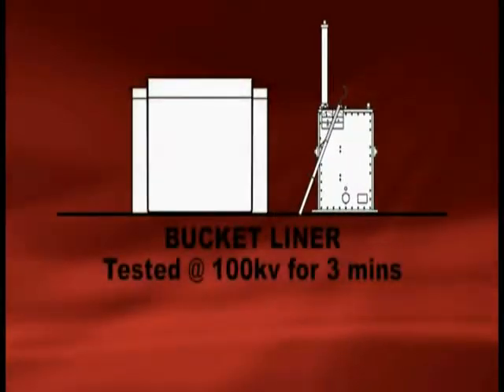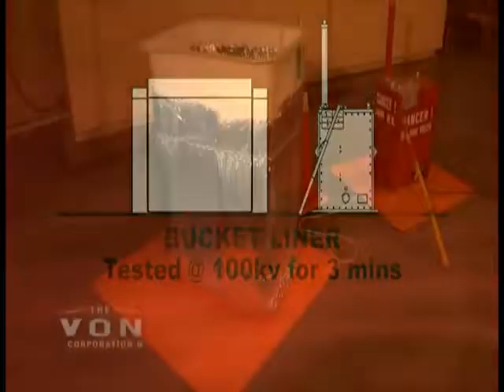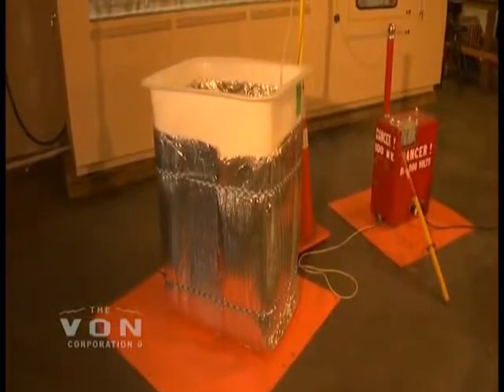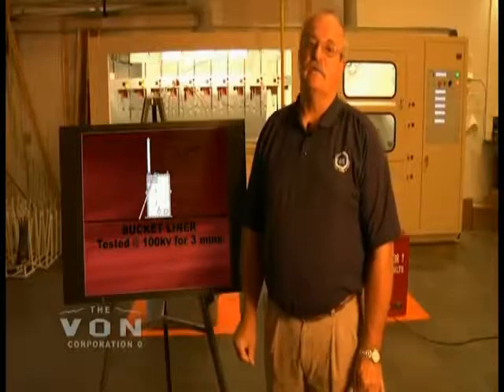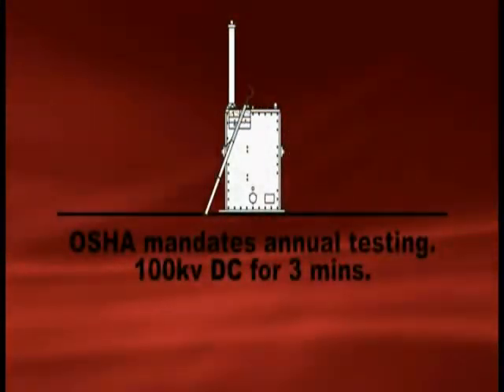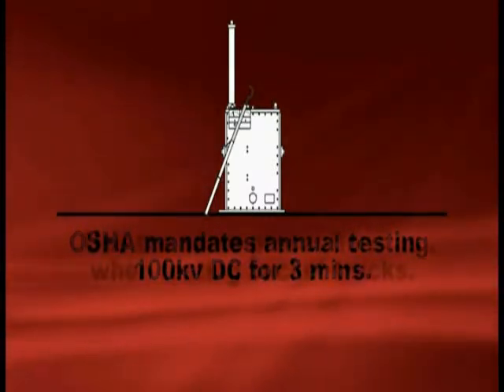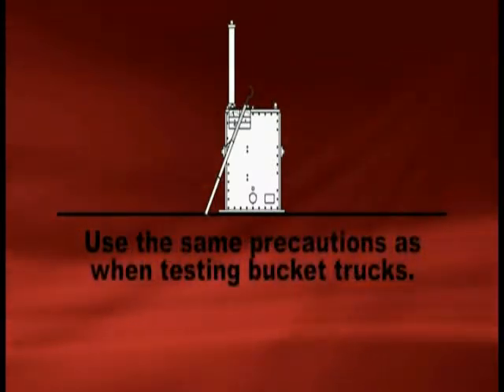We are now going to test a bucket liner. The bucket liner is to be tested at 100,000 volts for 3 minutes and cannot puncture. This test is mandated by OSHA, and the liner is for protection of the operator's feet in case the operator sets the unit down on a grounded conductor while having an energized conductor in his control.